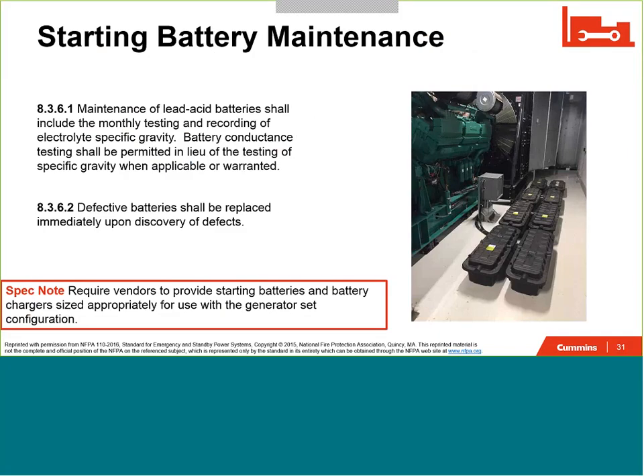The starting system is also one of the key failure modes, or key reasons for a fail to start on a generator set. So this is clearly called out by NFPA 110. Really the requirement here is to test, check and inspect those batteries to make sure that they are in good health and are being replaced when appropriate. We do always recommend that you yield to the generator manufacturer's expectations or guidelines for battery sizing, but also look to the generator manufacturer to provide a recommendation for the battery charger, in not only its amperage or ampacity rating, but also in its features and functions. That will help to maintain the batteries in their prime.